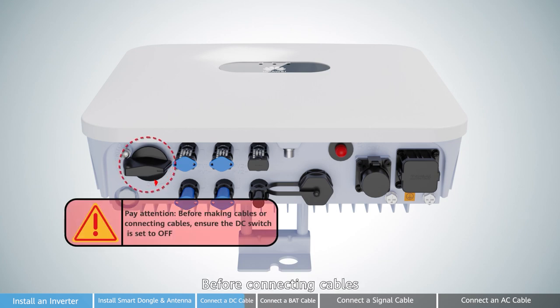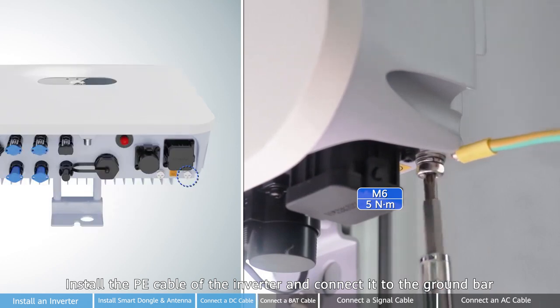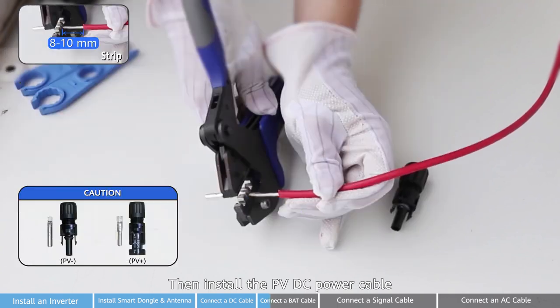Pay attention! Before connecting cables, ensure the DC switch is off. Install the PE cable of the inverter and connect it to the ground bar. Then install the PV DC power cable.